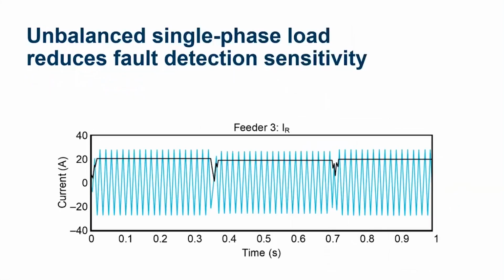Now, the challenge with this is that we can see in this case, and this is in a simulated fault scenario, we're actually introducing a fault on the system that actually improves that imbalance. And so when we introduce a high impedance fault, this 200 ohm fault, it actually reduces that residual, that zero sequence current that we're measuring, from 20 amps to 18 amps.